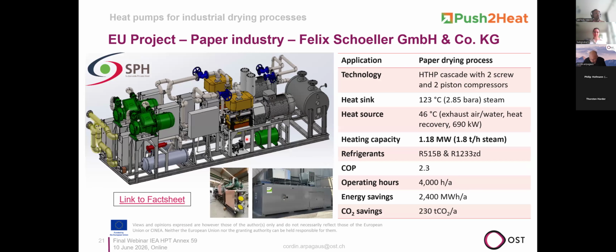Here we have a little bit of a bigger picture of this heat pump. So you see here 4 compressors. It's a cascade cycle with 2 refrigerants. On the bottom cycle, it's R515B, a synthetic refrigerant with screw compressors from Bitzer. And in the top cycle, 2 piston compressors from SPH that run also with HFO refrigerant. And here on the right, the steam generator heat exchanger that directly generates steam by condensing this R1233zd refrigerant.